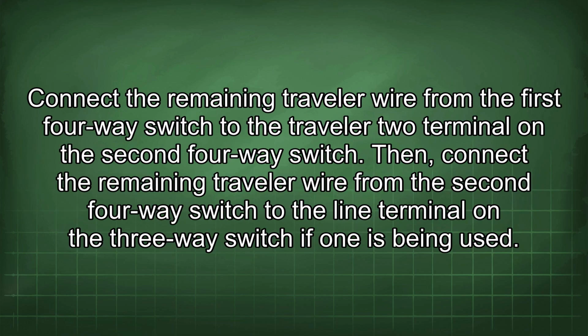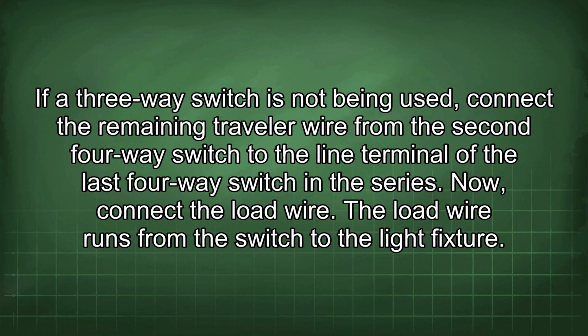Connect the remaining traveler wire from the first four-way switch to the traveler 2 terminal on the second four-way switch. Then connect the remaining traveler wire from the second four-way switch to the line terminal on the three-way switch if one is being used. If a three-way switch is not being used, connect the remaining traveler wire from the second four-way switch to the line terminal of the last four-way switch in the series.